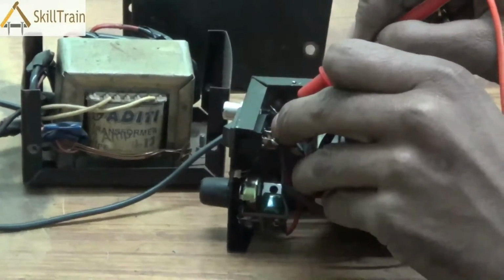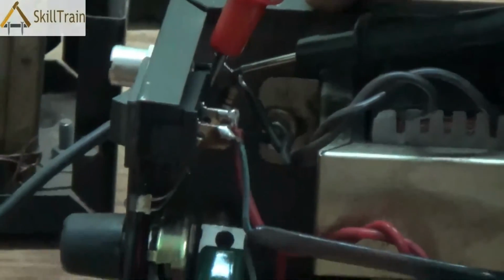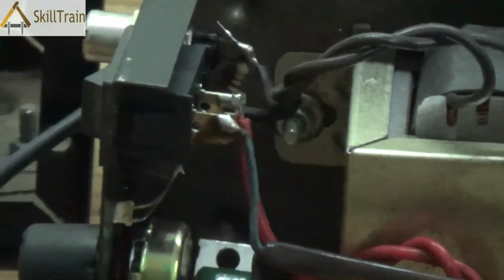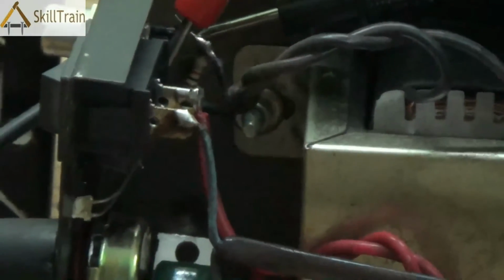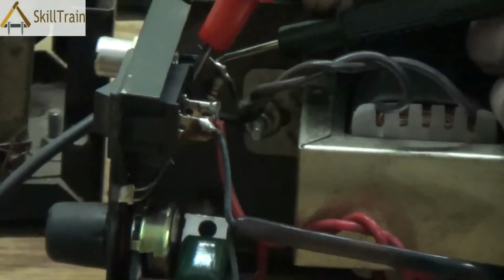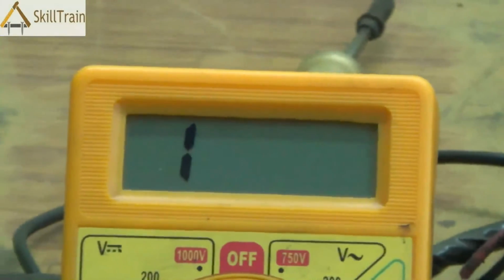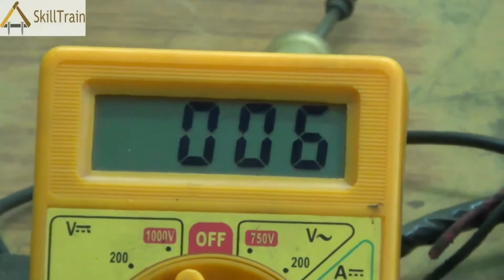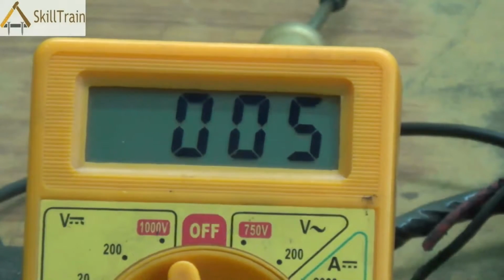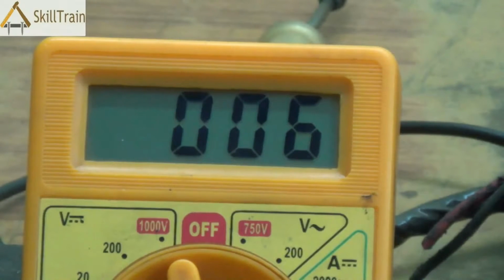Now, as you can see, these are the points where the black wires are soldered. So, if you hear the beep, as you can hear the beep, it means that the connectivity is intact. So, wherever the connecting wires are placed in the transformer, you check the connectivity at those points, you hear a beep, and it also shows the ohm reading on the screen. So, when we are checking the black wires, we are getting an ohm reading of roughly around 5 or 6 ohms. It basically means that the resistance at that point is actually 5 ohms. Because there is a coil inside, it measures the resistance also and shows you the resistance.